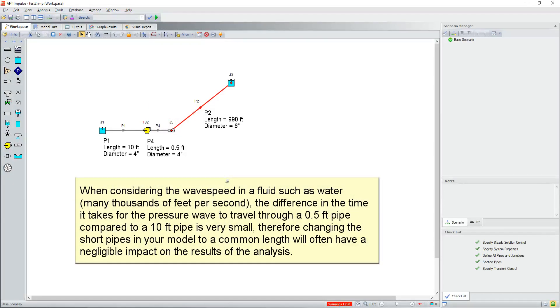When considering the wave speed in the fluid, such as water, many thousands of feet per second, the difference in time it takes for the pressure wave to travel through a half a foot long pipe compared to a 10 foot pipe is very small. Therefore, changing the short pipes in your model to a common length will often have a negligible impact on the results of the analysis.